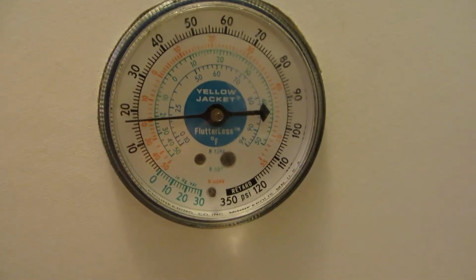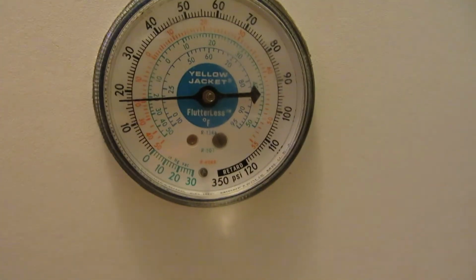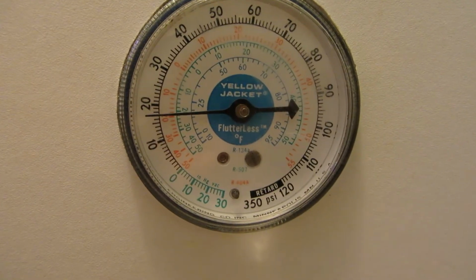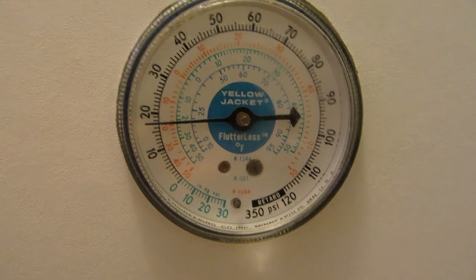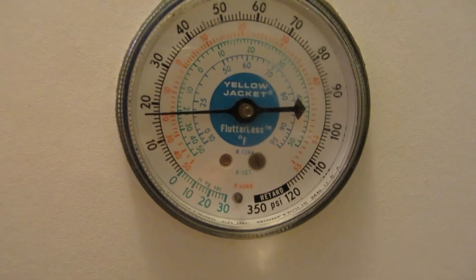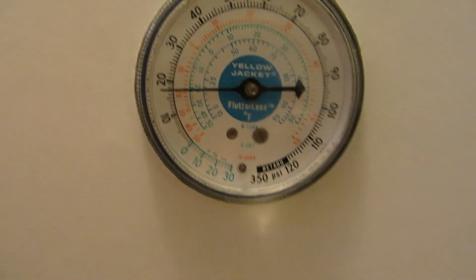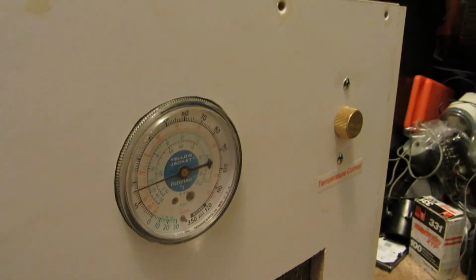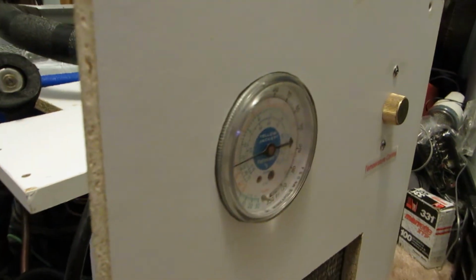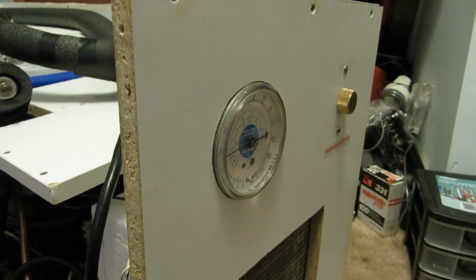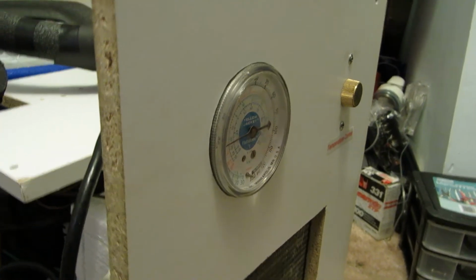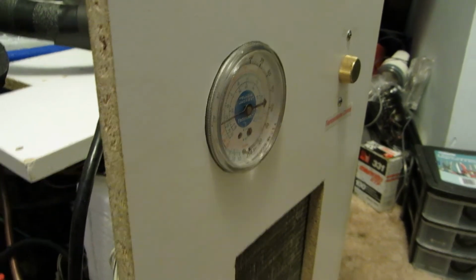So I've got the CPEV valve set to maintain a constant pressure of about 17 psi. Now it won't actually take very long for this to cycle off. I've got this at the bare minimum setting and it won't take very long at all. Maybe within 5, maybe 10 minutes it'll cycle off already.